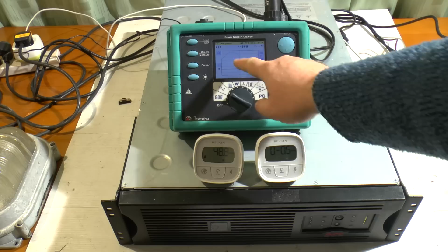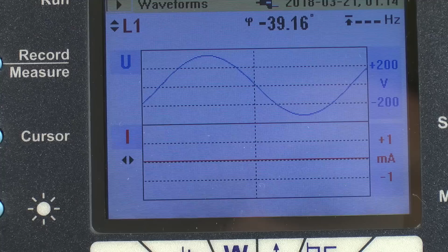What's interesting now is if you watch this waveform, that's a little bit rough. That's the existing input waveform. But the UPS's own waveform is lovely and smooth compared to that. And with the UPS switched on but not running any load, you can see it's wandering back down. So there's not much of a difference whether it's switched on or switched off, to be honest. Let's give it a 100 watt load, and that's probably helping with the power factor, I should think, as well. I can switch that to a 1000 watt load.